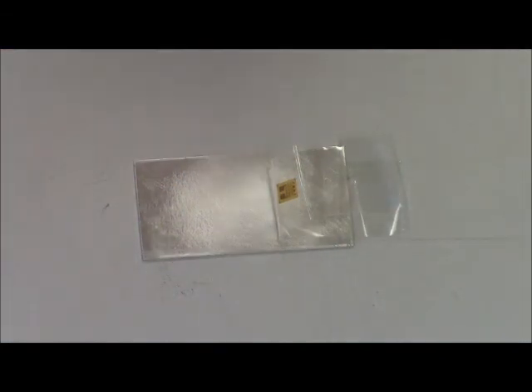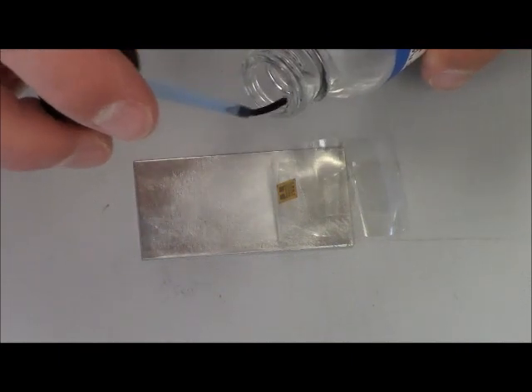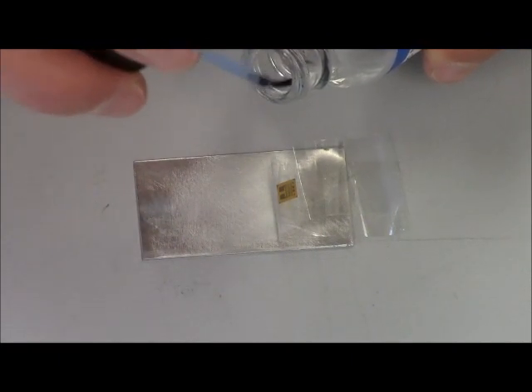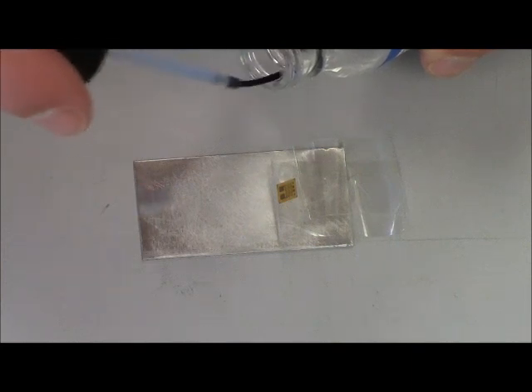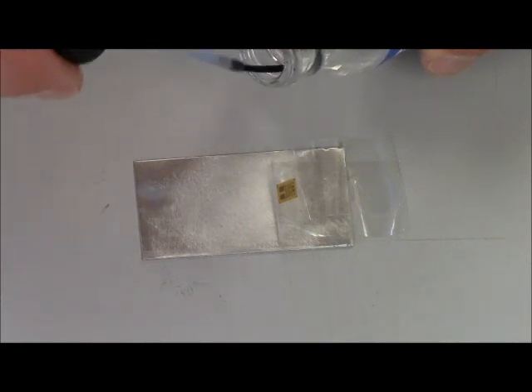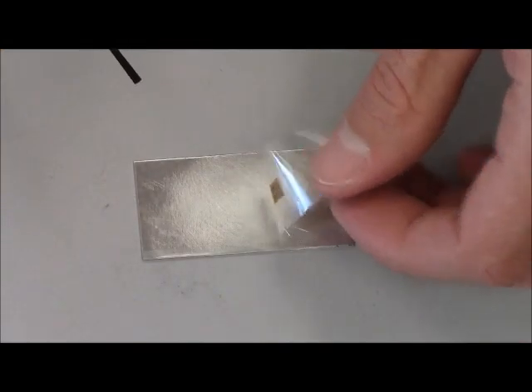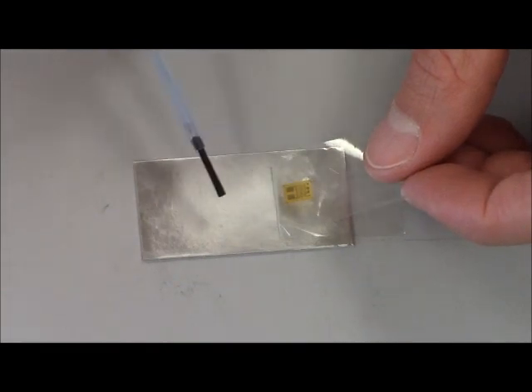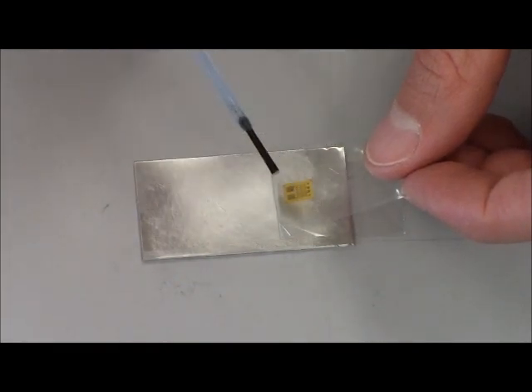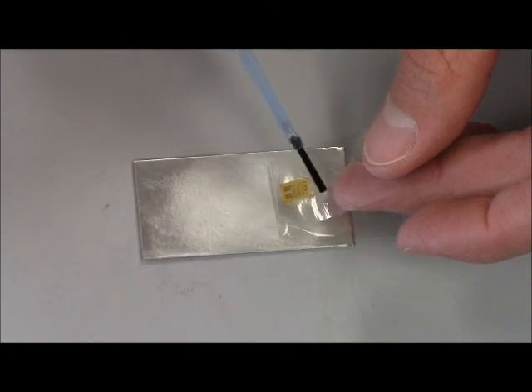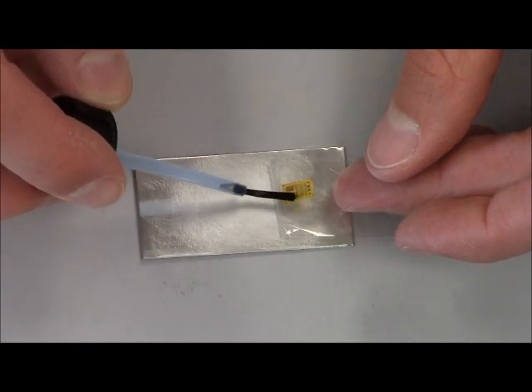At this point, I'm going to apply a catalyst. This catalyst will prepare the surface for the super glue. When I take the brush out of the bottle, I'm going to swipe it on the neck ten times or so. We don't want a lot of this, just enough to put a thin film over the back side of the gauge. We want to make motions that go across the entire length. If you go halfway and pull up, you'll leave a pool of this, which takes longer to dry. So using a sweeping action all the way across.